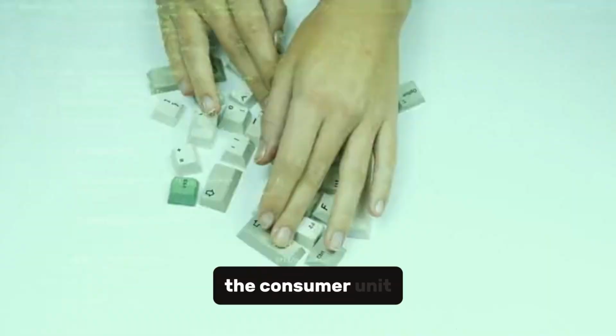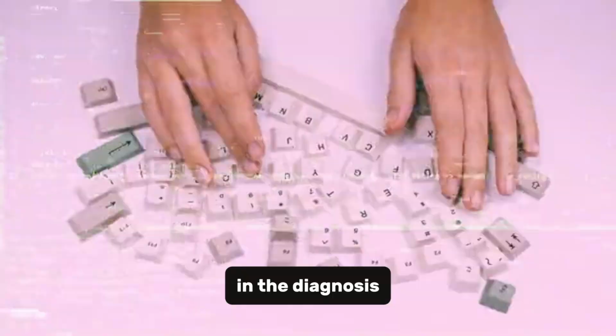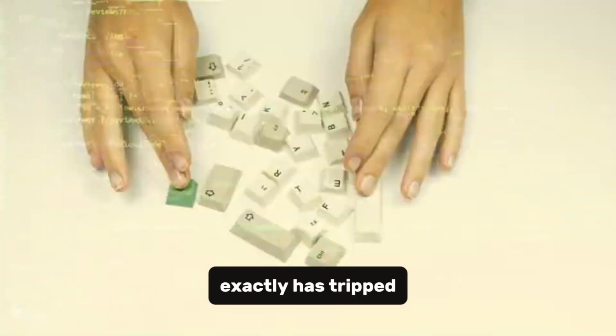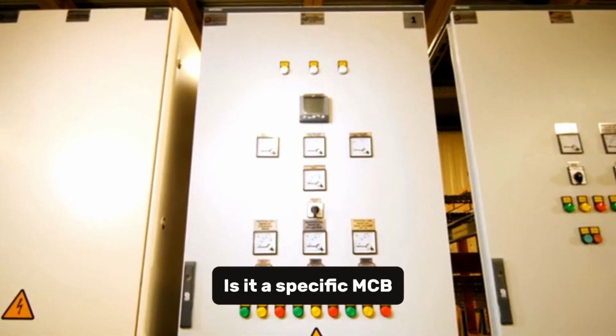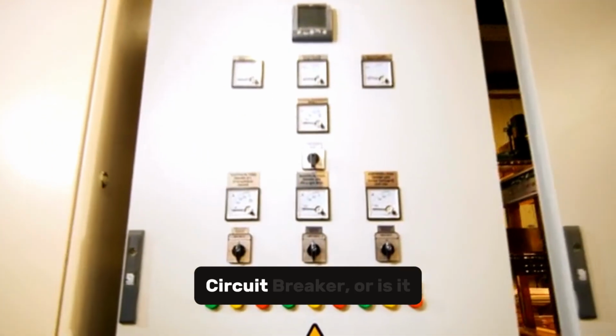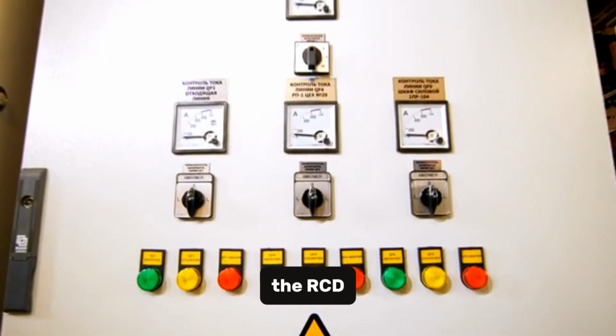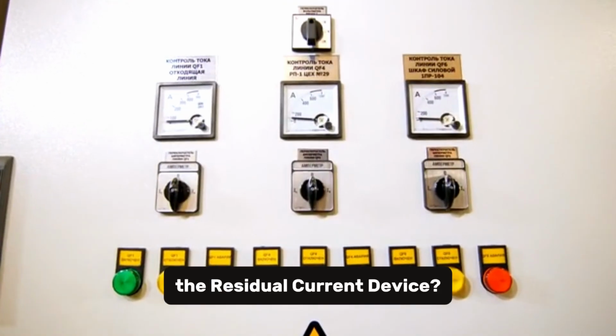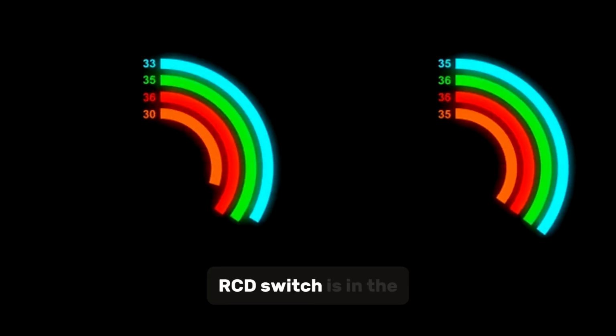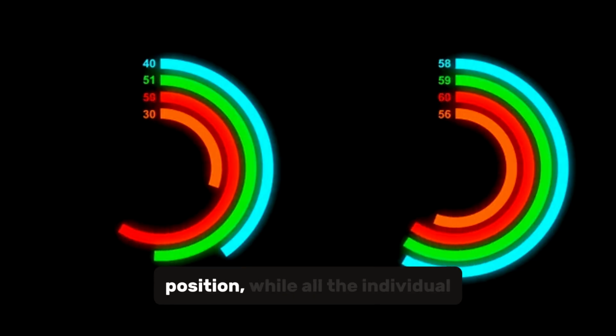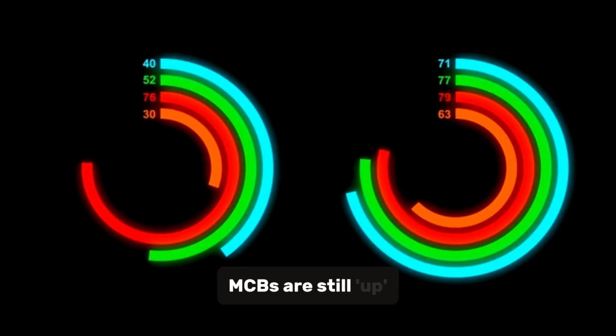Alright, here we are at the consumer unit. Now, this is a critical step in the diagnosis. I need to identify what exactly has tripped. Is it a specific MCB, which stands for miniature circuit breaker? Or is it the RCD, the residual current device? I take a close look at the board, and there it is. The main RCD switch is in the down or off position, while all the individual MCBs are still up.